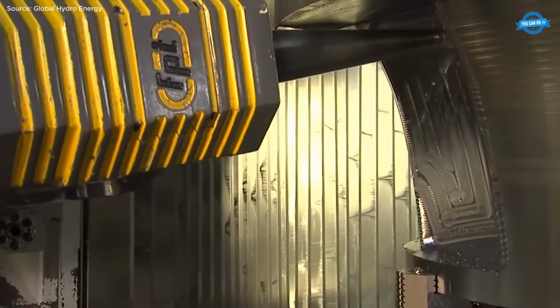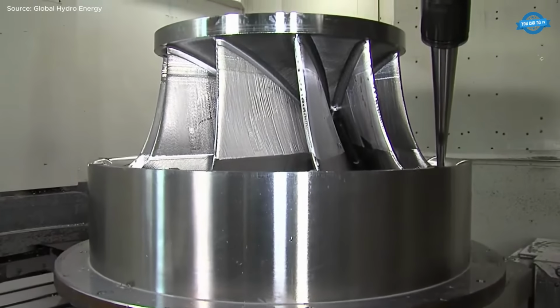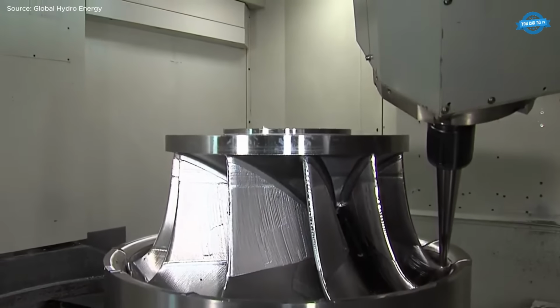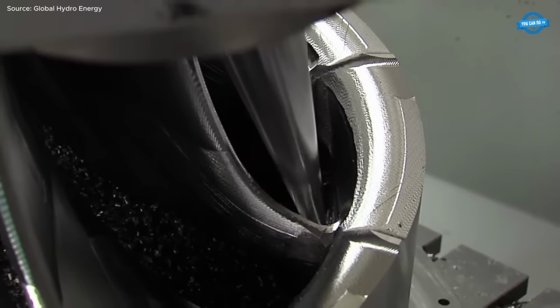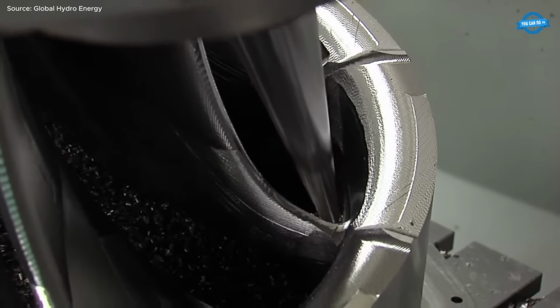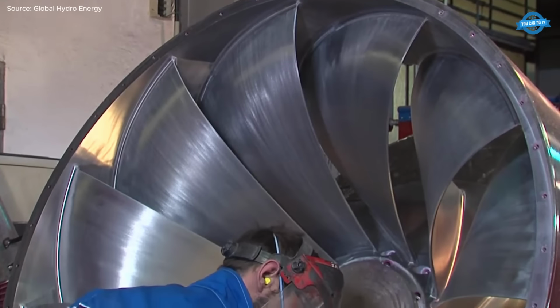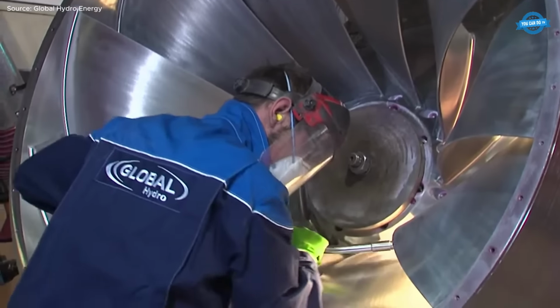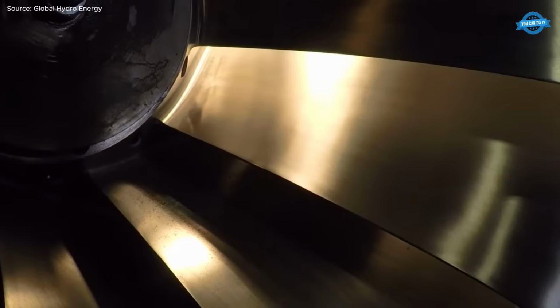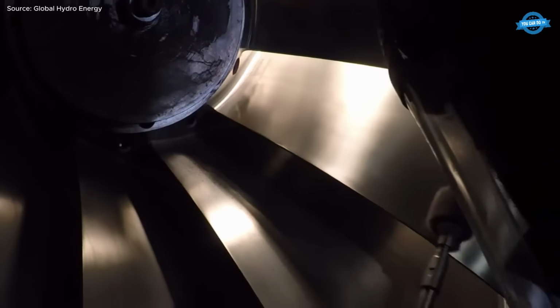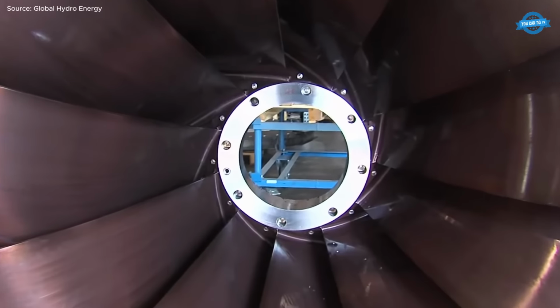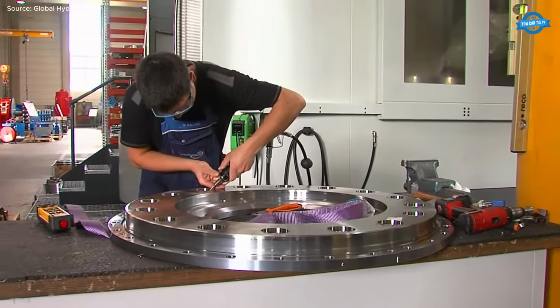Once the 3D design is finalized, CAM programming and machining simulations define milling duration, material removal rates, and collision control. The runner is typically machined from 1 or 2 forged monoblocks of high-alloy stainless steel, selected for strength and erosion resistance. Using a 7-axis CNC machining center, complex blade geometries are milled in a single setup, with machining times reaching up to 400 hours depending on size and material.